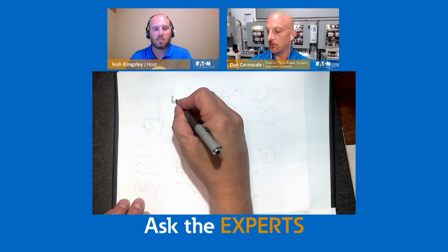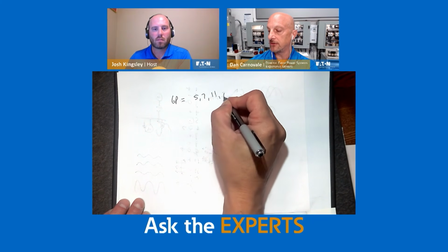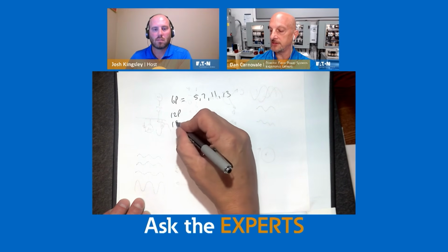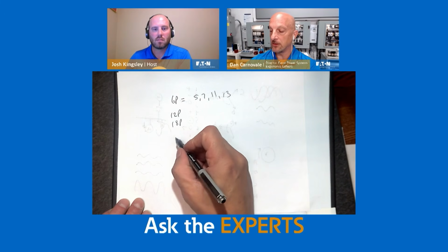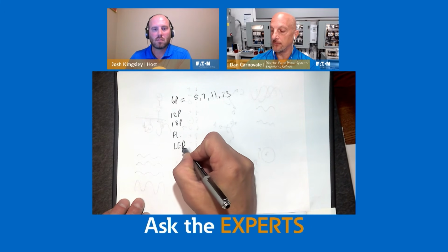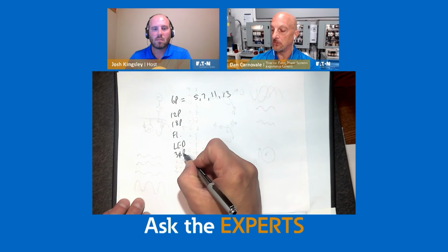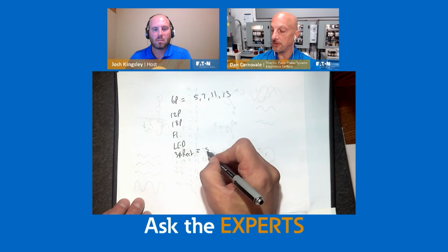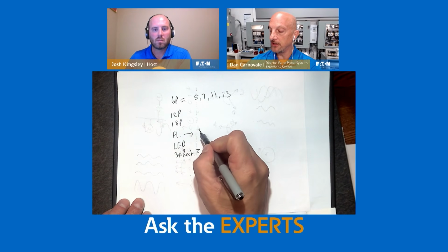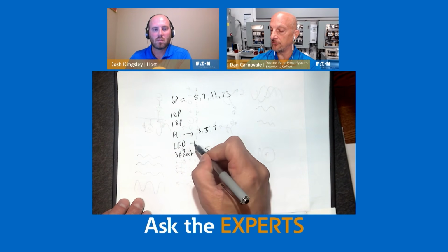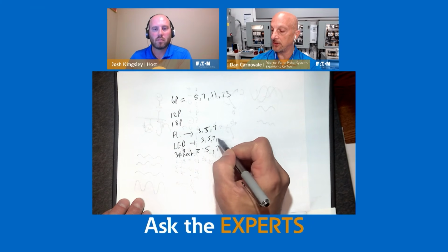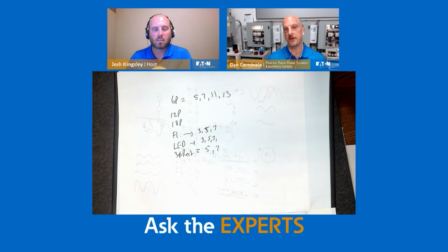And if you look at VFDs, we say 6 pulse, we already said 5th, 7th, 11th, 13th; 12 pulse, we could figure that out; 18 pulse, we could figure that out. But like fluorescent lights or LEDs or maybe a 3-phase rectifier for vehicle charging, for example, that might have 5th, 7th, whatever. This might have 3rd, 5th, 7th. LEDs might have 3rd, 5th, 7th, but they might be a different spectrum, a different pattern. The nice thing about harmonics is they're pretty predictable in terms of the characteristic harmonics, meaning the signature associated with each type of harmonic. So hope that helps answer the question a little bit.